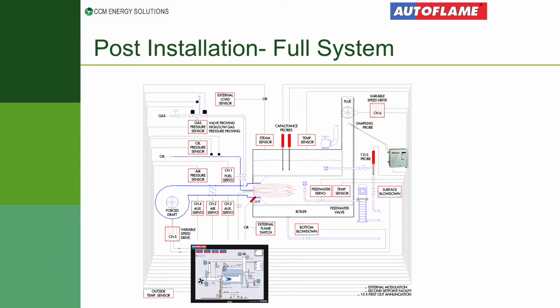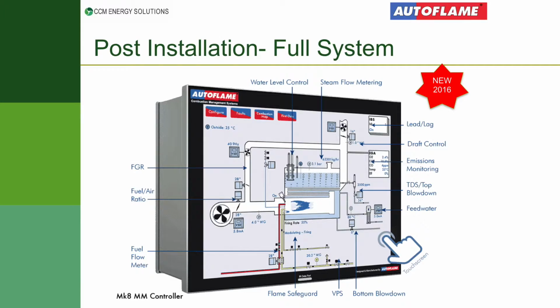What we want to do is strip all of that off. All the individual components we're going to get rid of, and everything is now wired through this unit. And this is the first look of this unit in Australia. This only got released 2 weeks ago. This is their new flagship, the Mark 8. It incorporates everything that you need on the boiler. And as you can see here, servo motors, variable speed drives, scanners, temperature sensors, steam sensors, analyzers, everything is incorporated into that one unit. This is a 12.1 inch touchscreen display, multi-touch capacitive screen display.